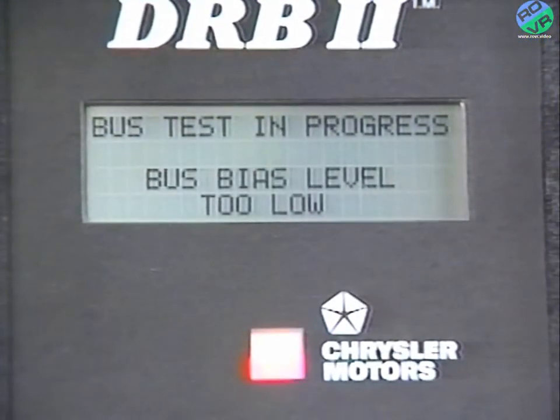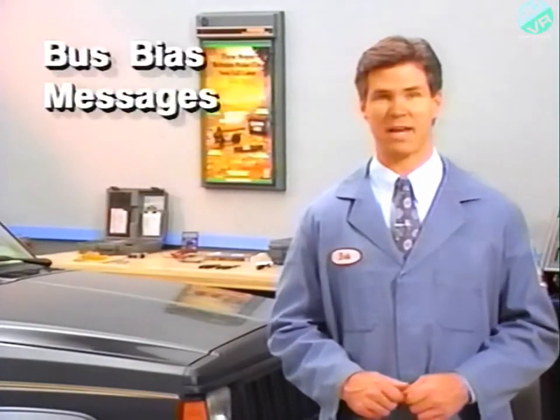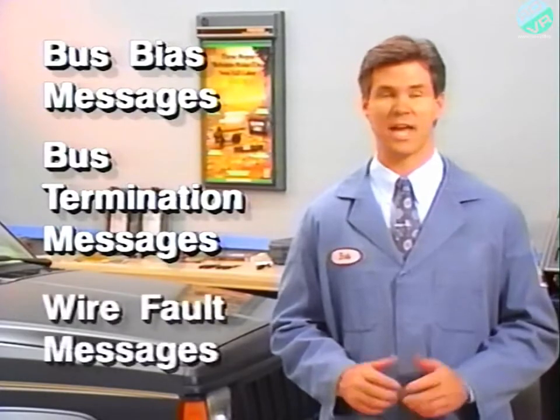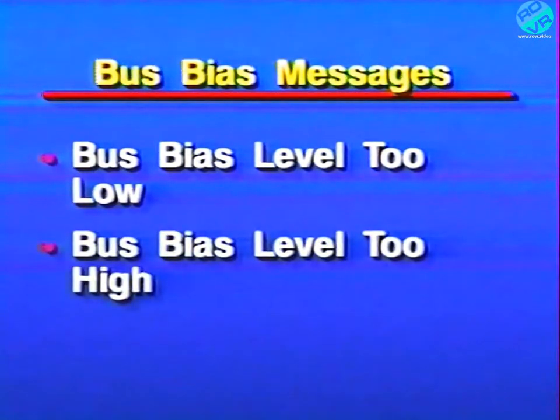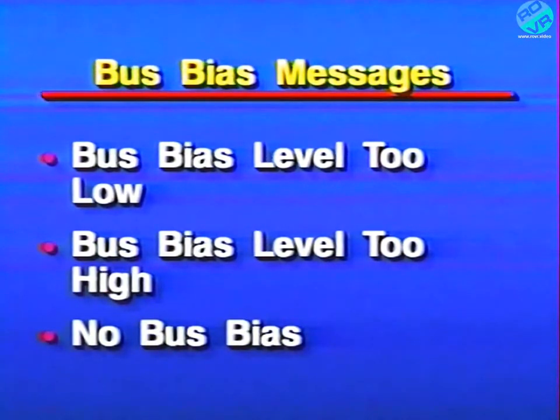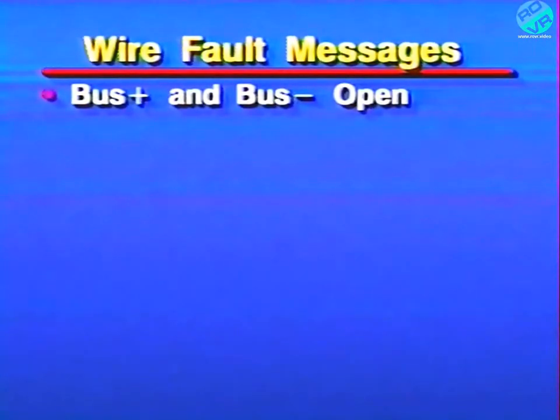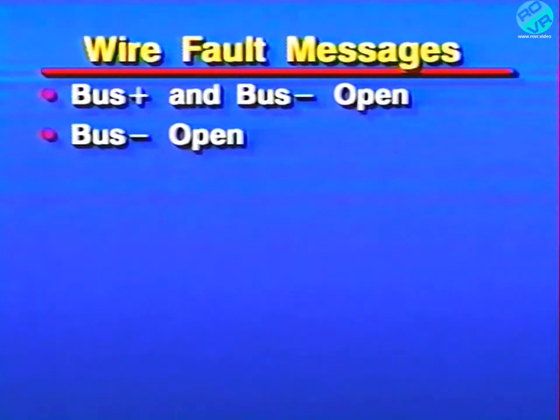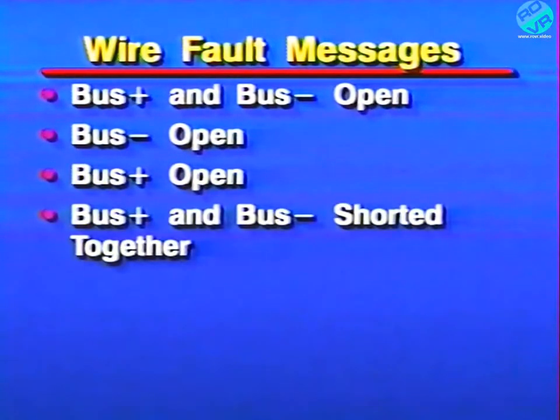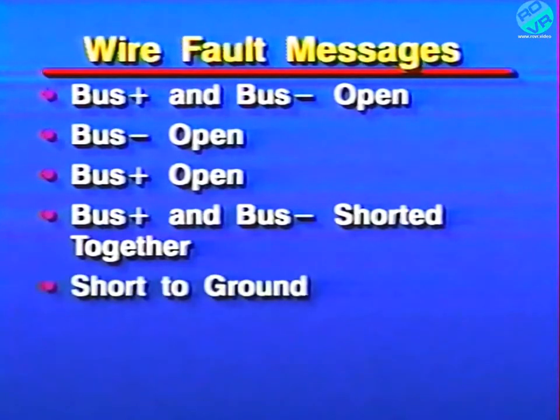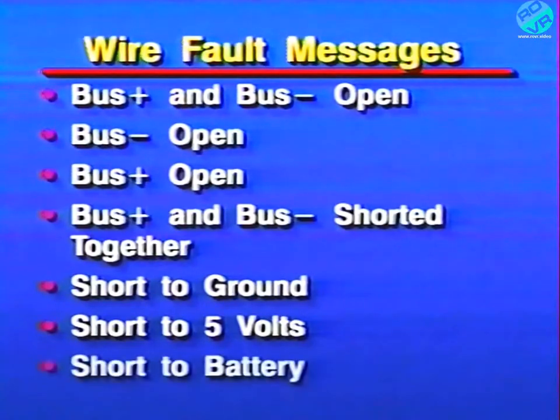If, however, there is a failure, a fault message will appear on the DRB2 and the bus will not be operational. The bus fault messages will fall into 3 categories: bus bias messages, bus termination messages, and wire fault messages. The bus bias messages are bus bias level too low, bus bias level too high, and no bus bias. The only bus termination message is no bus termination. The wire fault messages are more numerous. They include bus plus and bus minus open, bus minus open, bus plus open, bus plus and bus minus shorted together, short to ground, short to 5 volts, and short to battery.